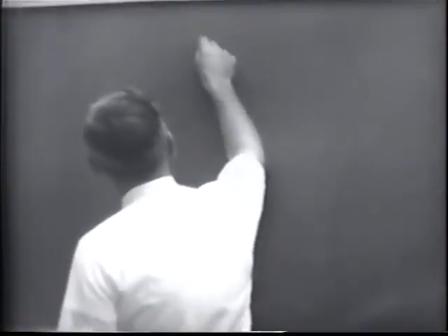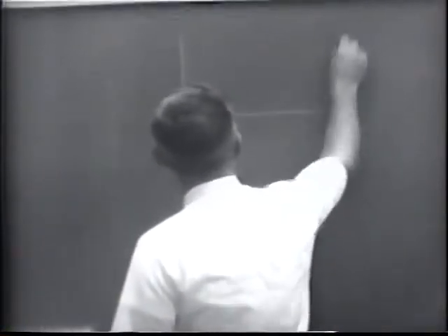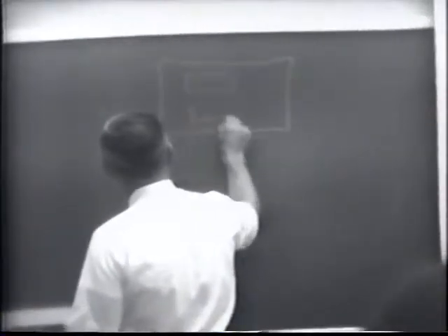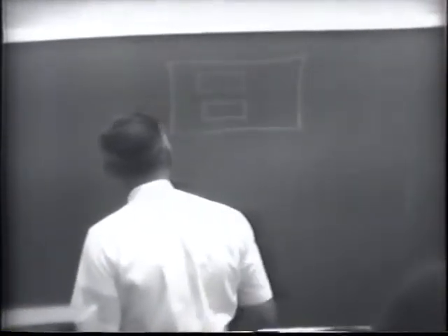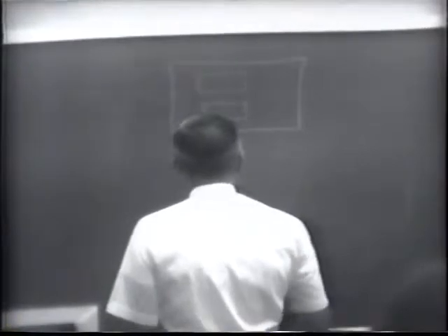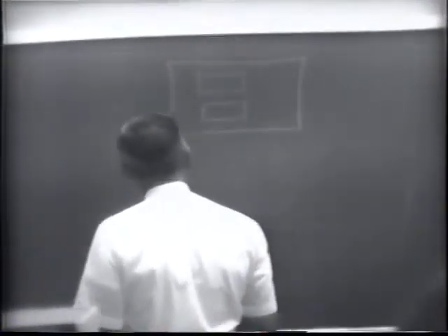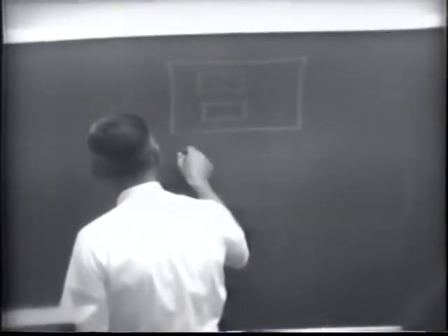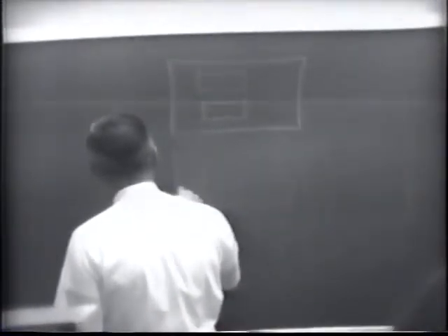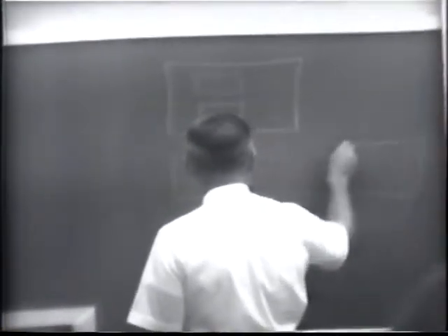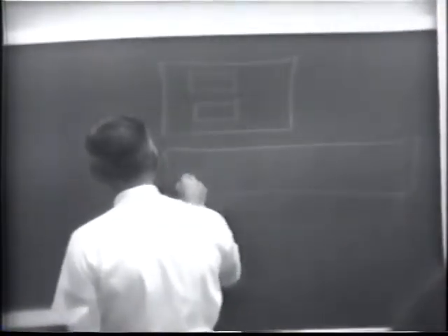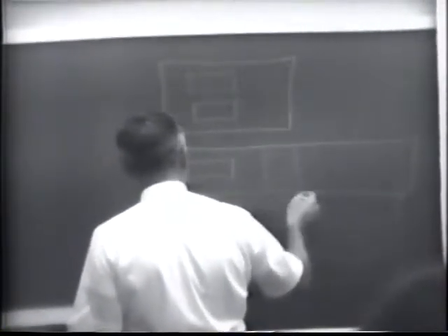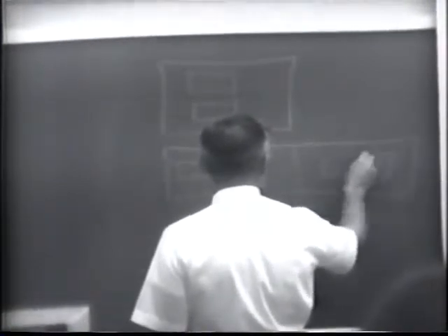So essentially, if you're looking down at the top, we have a structure like this with a transformer setting there and a transformer setting there. Now that takes up a little better than 11 feet, almost 12 in width across here. So if we get a sidewalk that is not wide enough for that, then we might go to a longer narrow type, which has a transformer setting here with a bus room in here for terminating the secondary cables and another transformer setting over here.